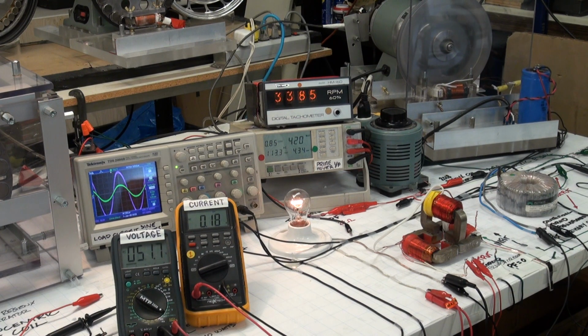The prime mover is delivering additional mechanical power to the drive shaft. We can see on the oscilloscope that the voltage and current sine waves in the primary of the conventional transformer are in phase, and that means that the primary of the conventional transformer is consuming real power and delivering real power to the load at less than 100% efficiency, as all transformers do.